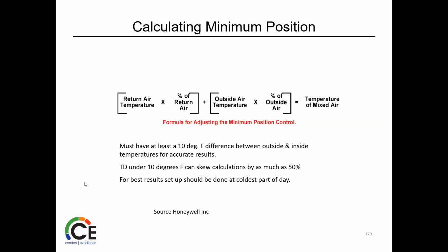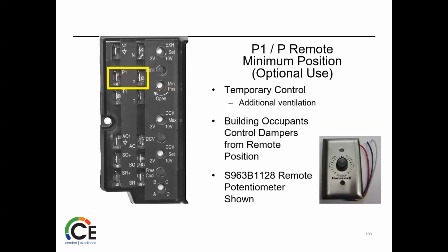For best results, setup should be done on the coldest part of the day. We're trying to set up for free cooling, so try and do it when there's the biggest load. P1 and P, the remote potentiometer, is located in the occupied space. It can be added if you want. This is an addition, not a need. But if somebody wants to be down there messing with it, you can obviously put in a remote one and let them do that. That's what these terminals are for.